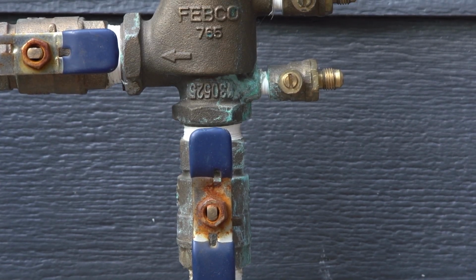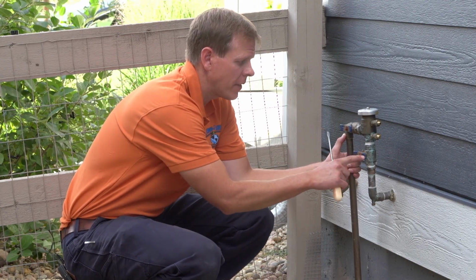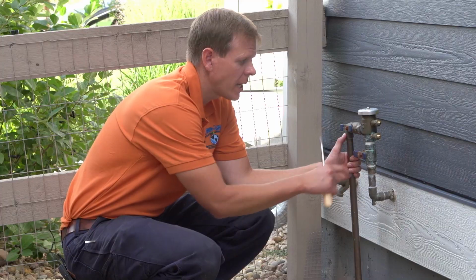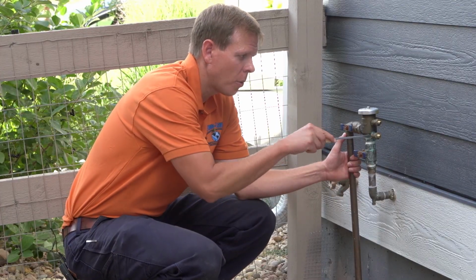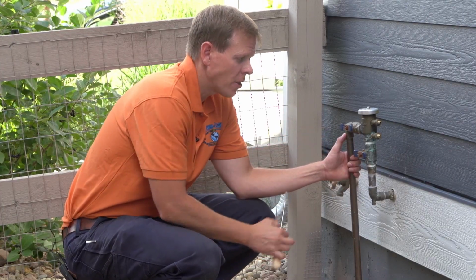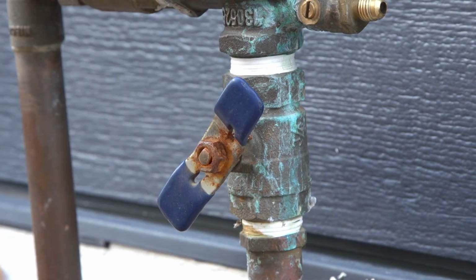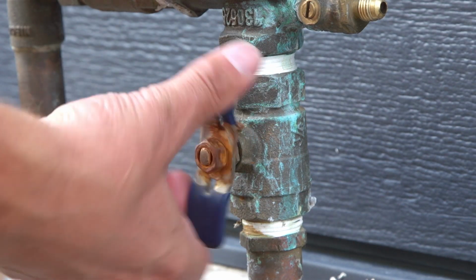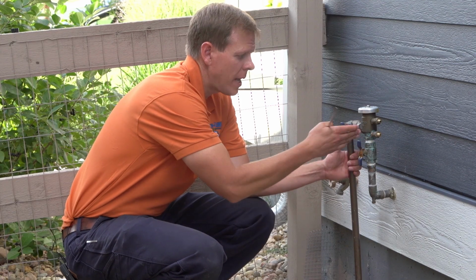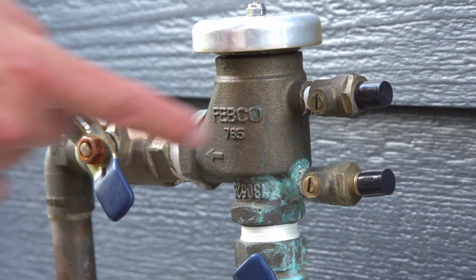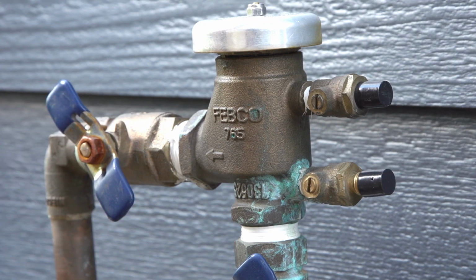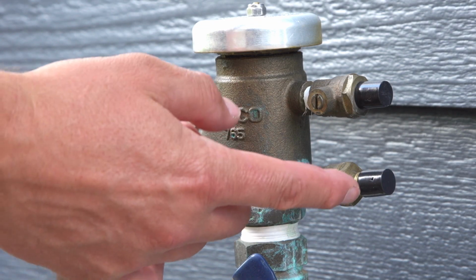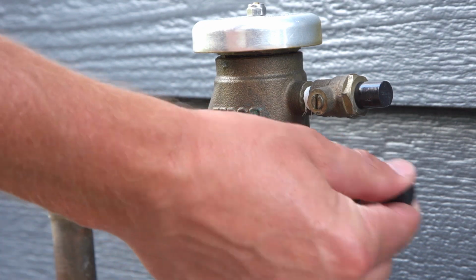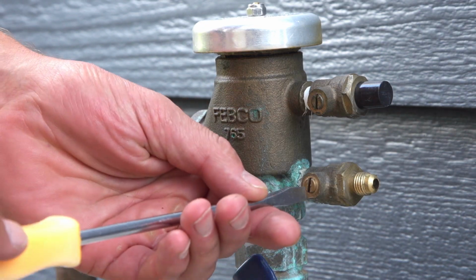It is very important that if you find that this ball valve is closed at a 90-degree angle, when you come out to open one of these test cocks, you remember to open this to a 45-degree angle or at least parallel, and that will allow air into the pipe. If your test cocks have plastic caps on the end of them, these actually don't really do anything, and you do need to remove them to get airflow into the system.